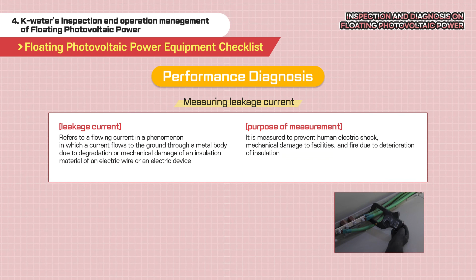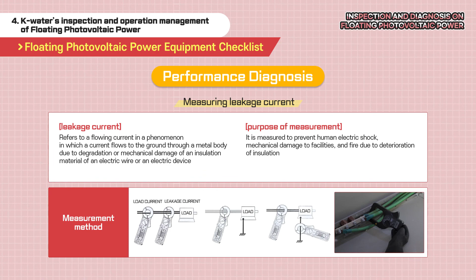Let's find out about the measurement of leakage current. A short circuit refers to a phenomenon where the cover of the wire or the insulation of the electric device degrades and the current flows to the ground through the metal body. At this time, the flowing current is called a leakage current. As shown in the figures, the leakage current measurement method measures the leakage current using a clamp meter by clamping the power cable for live wires in a lump, and takes an action for the failure if the measured value exceeds the standard value.